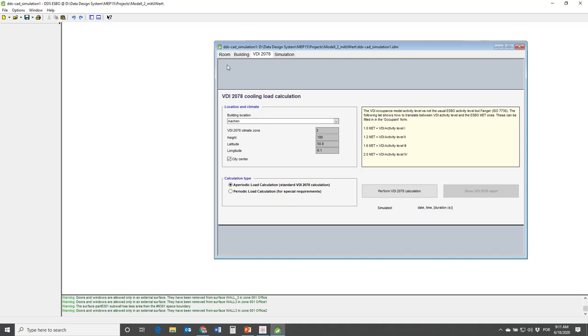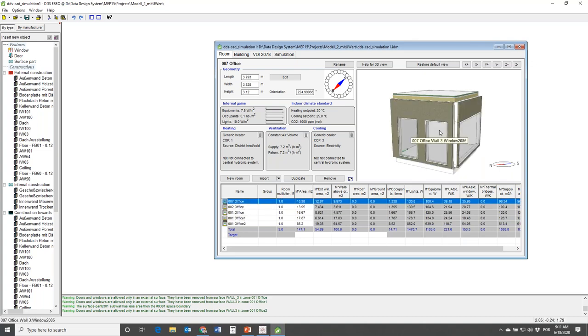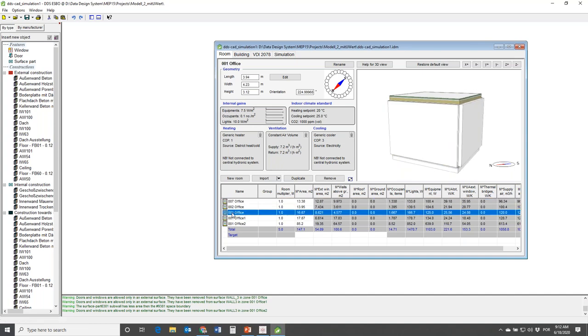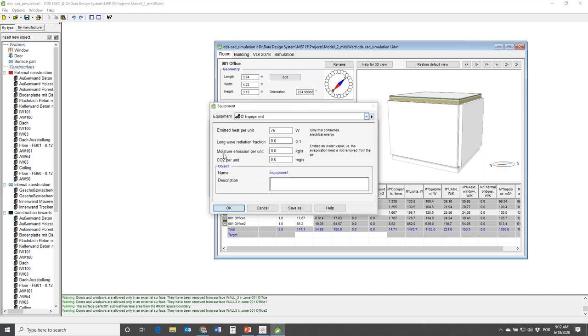Let's go back to the Room tab and look at the data we can specify for the different rooms. When clicking on a room, the display changes and the data changes. Let's go to Room 001 Office and start with the internal gains - relevant to the cooling load calculation. We look at heat gains from equipment, occupants, and lighting. Under Equipment, you can specify the heat emitted in watts per square meter.